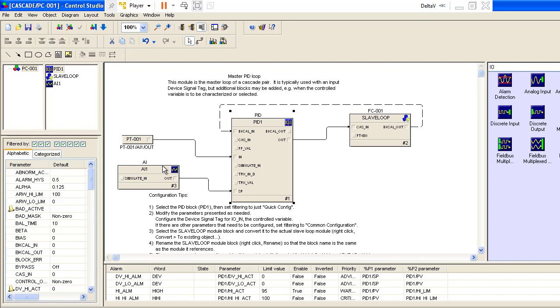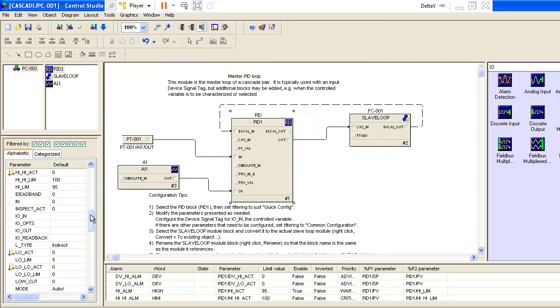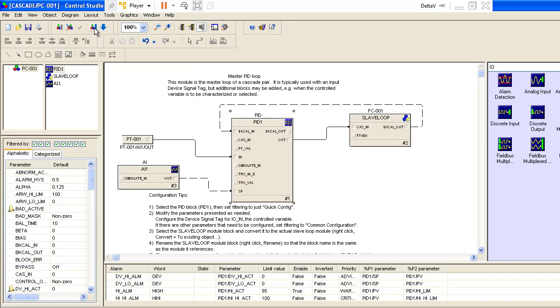You could see that this module's set point is going to be linked to the HMI. You probably wouldn't even need this to start with, but just for this simulation, we're going to use this AI block. In the next video, we're going to connect this to our HMI and see how we can also do that for the operators — so they wouldn't have to come to this back end to actually change values. We're supposed to set the parameters for this. For a cascade system, the master would have to be in auto mode — but this would be changed by the operator. So I will save this and assign this, and then download this module.